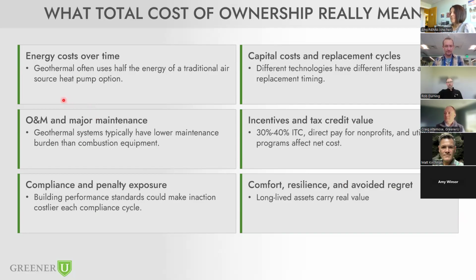In general, on energy costs over time, an air source heat pump project is going to run around 200% efficient, which means for every kWh of input into that heat pump, it's going to create double the amount of heat output. But as I mentioned, it's having to create that heat whether it's 0 degrees outside or 50 degrees outside, and it can't do that as efficiently the lower the outside air temperatures go. For a geothermal system, where you're talking about a very stable medium year round, you can run that system closer to 400% efficiency, and those are real world efficiencies that we're seeing. So if you're going to completely electrify and you're afraid of that sticker shock on your first electric bill, geothermal is going to help alleviate that by creating almost twice as much energy savings long term.